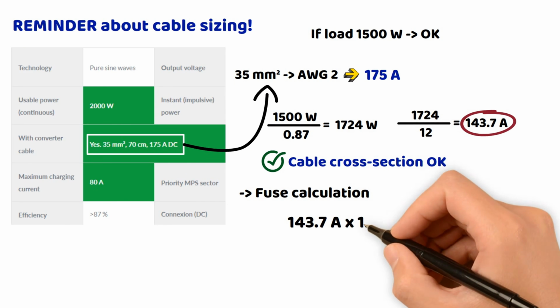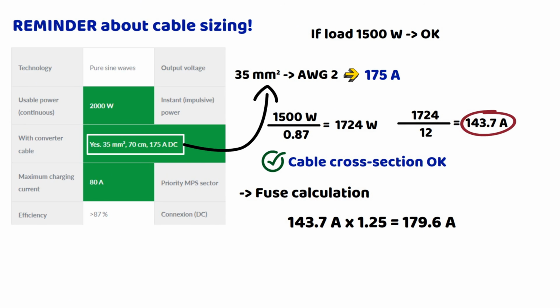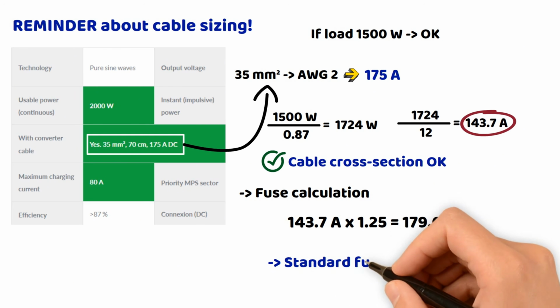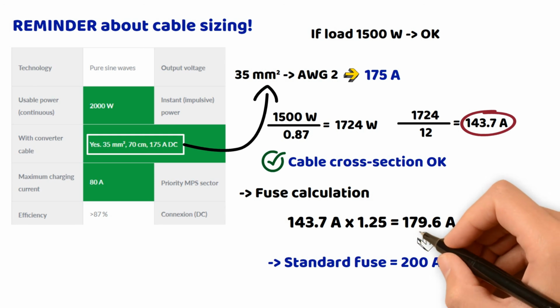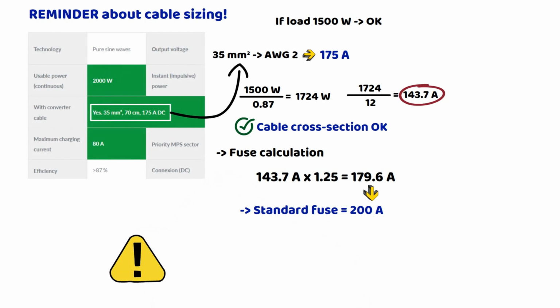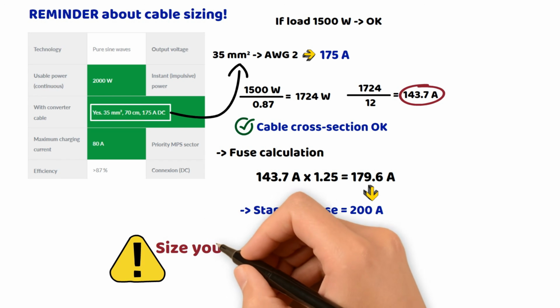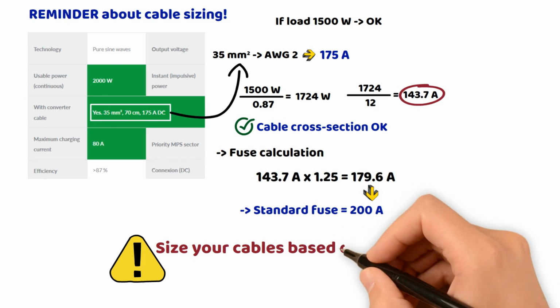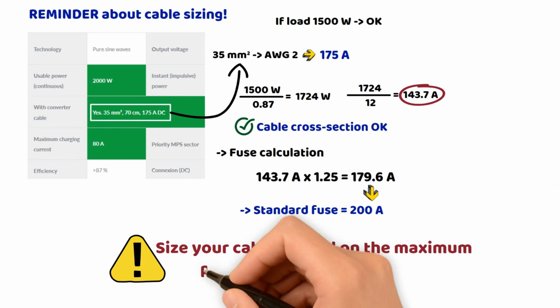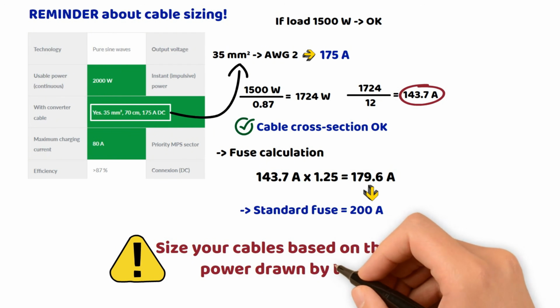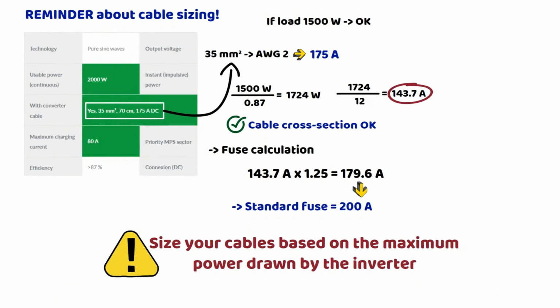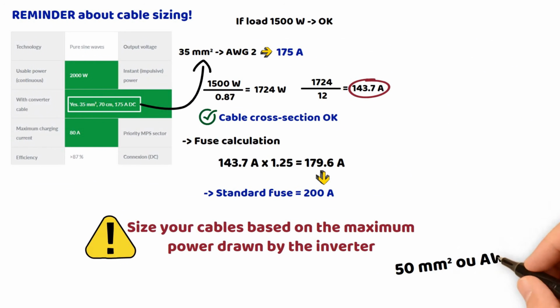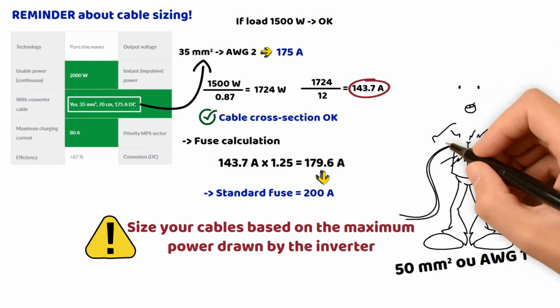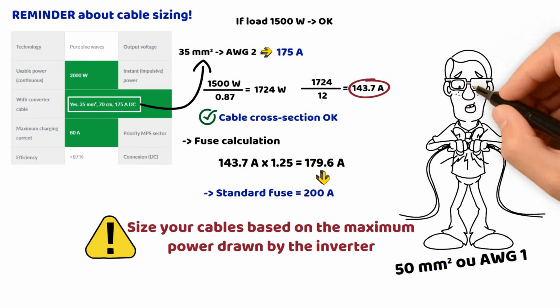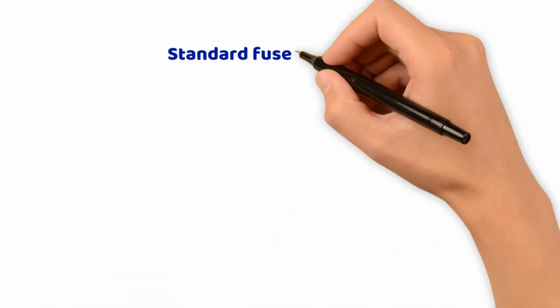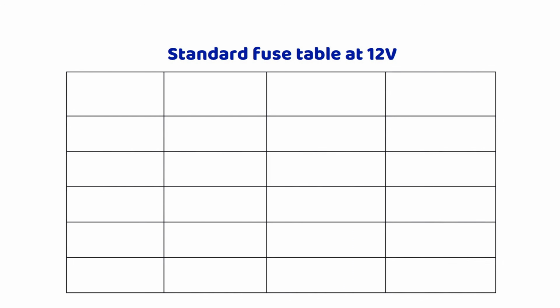We can even continue the exercise all the way to calculating the fuse. 143.7 amperes multiplied by 1.25 equals 179.6 amperes. So in this specific case, you would choose a standard 200 ampere fuse. However, the problem here is that the inverter can go much further. And over time, who can remember that the cables are not sized for the maximum power of the inverter? Even if you only use 1500 watts, if you install a 200 or 250 amp fuse rated for the maximum power of the inverter, you must absolutely install cables that can handle more than 250 amps, such as 50 square millimeters or AWG1, because the fuse will not protect your 35 square millimeter or AWG2 cable in the event of a prolonged overload at 2000 watts.